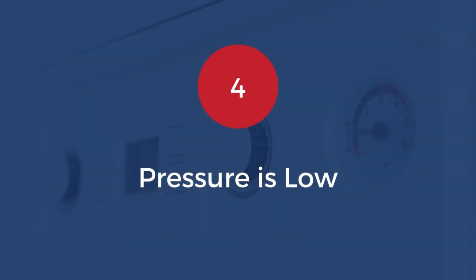4. Pressure is low. You'll know your pressure has declined to unacceptable levels if the pressure gauge drops below 1. This can be caused by water leaks, a failing pressure valve, or by a recent bleeding of the system. If the latter can be ruled out, you should call your HVAC contractor to ask for assistance.